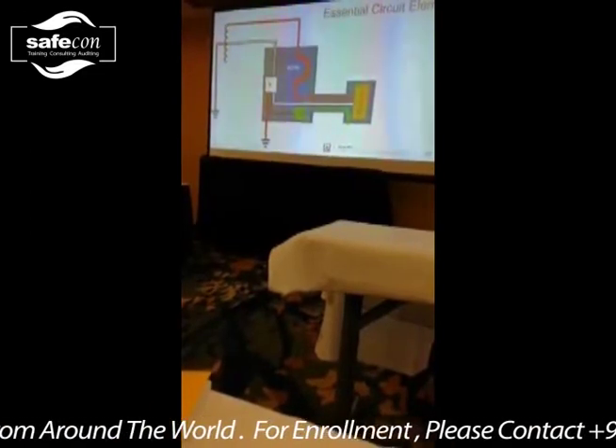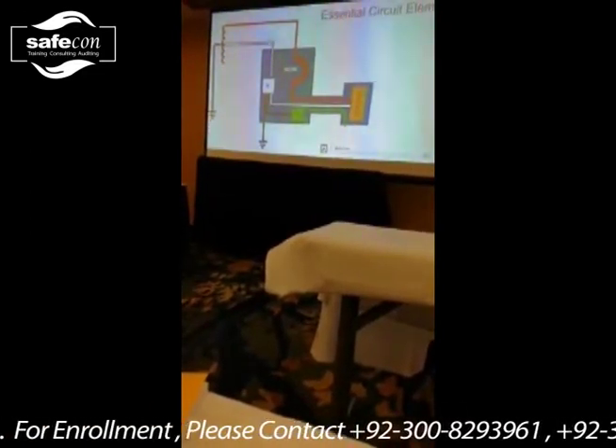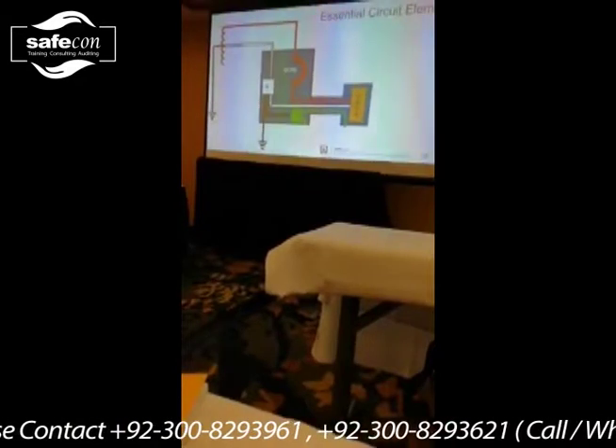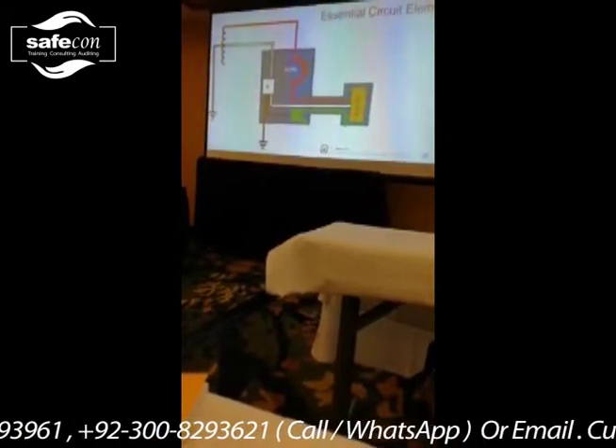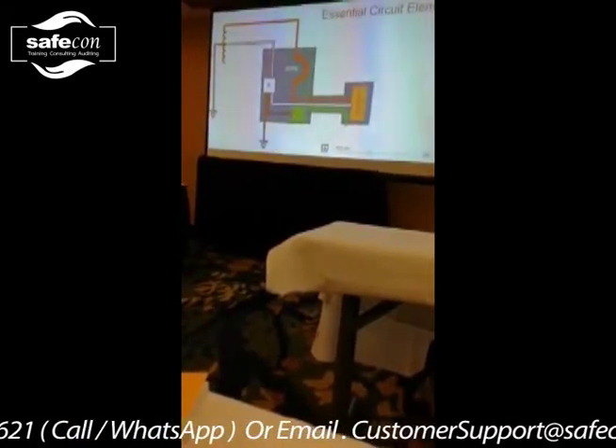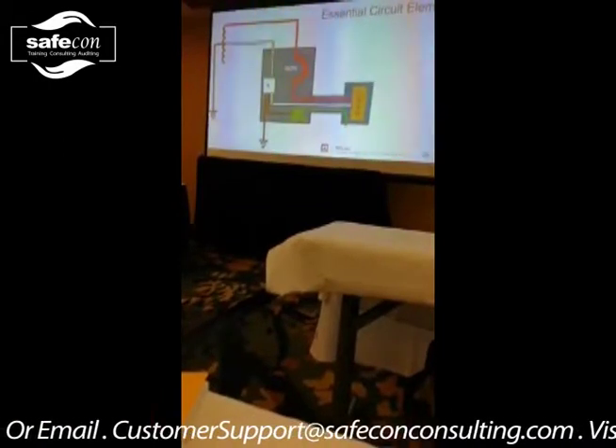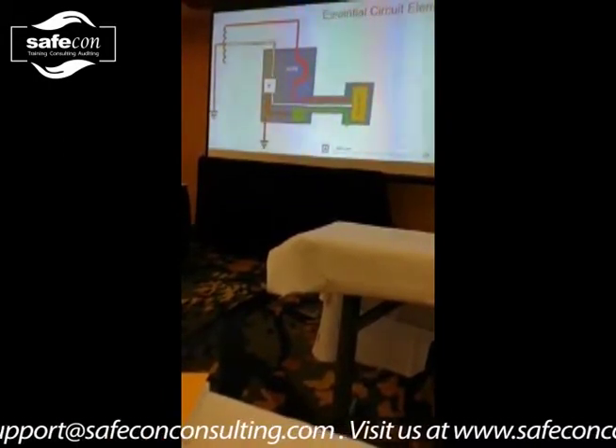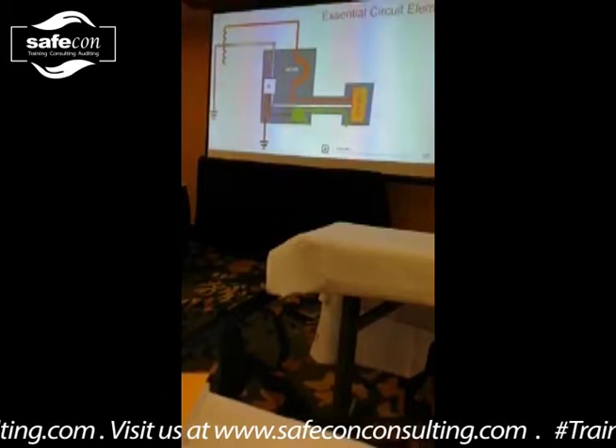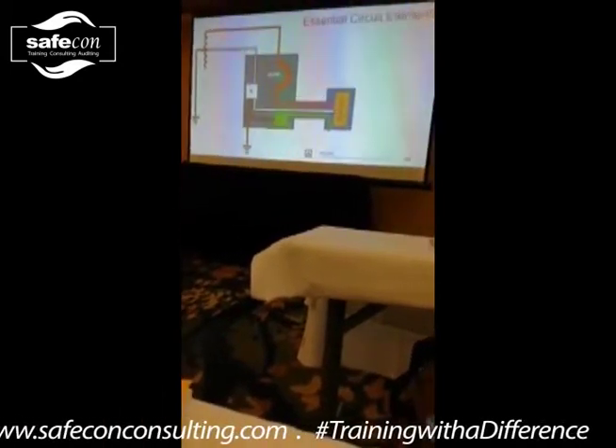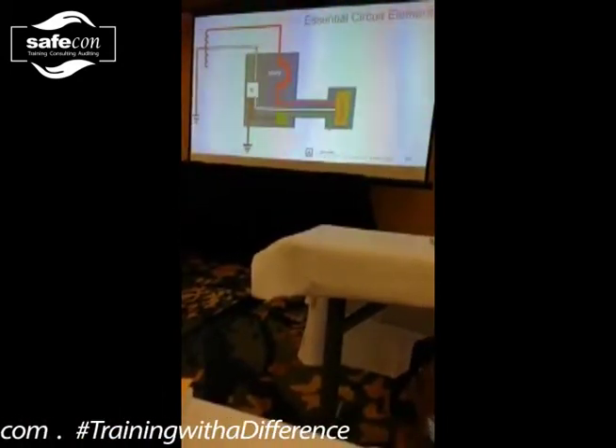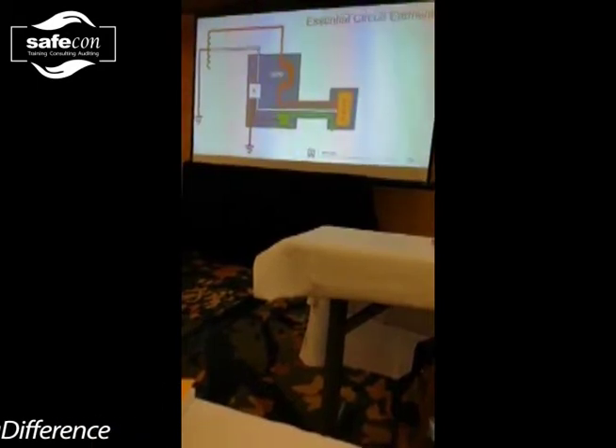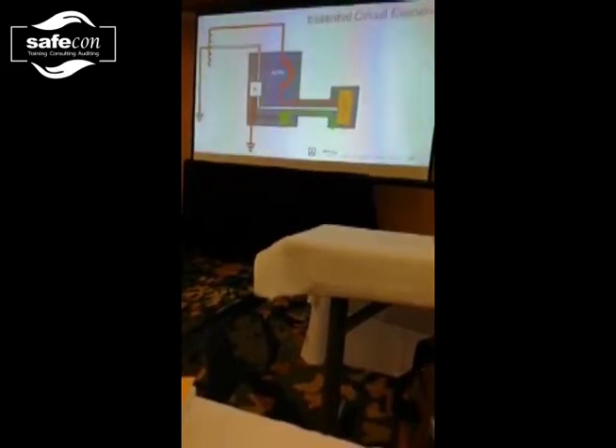In that case, it was a system bonding jumper. This component right here was compromised in that installation, and so there was no way for the current to get from this point, from the enclosure, onto the grounded conductor and back to the source. And that's why the device never opened. It actually burned a hole in the metal enough so that the arc kept far enough apart that it couldn't sustain itself, and it stopped arcing.